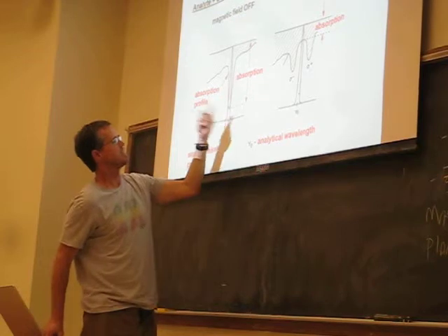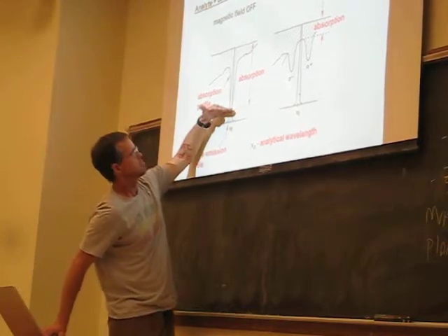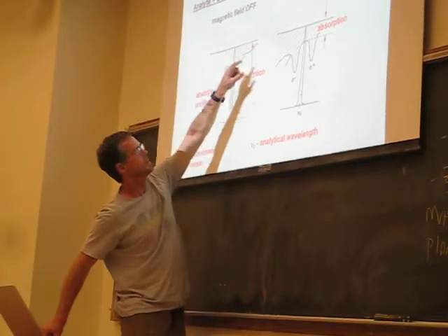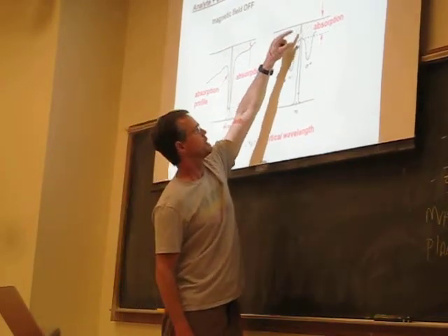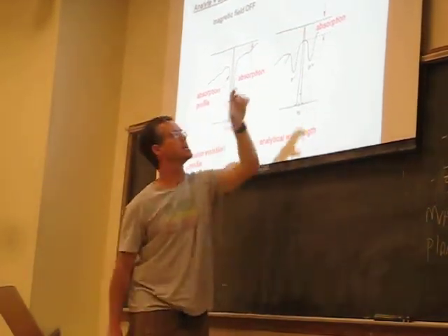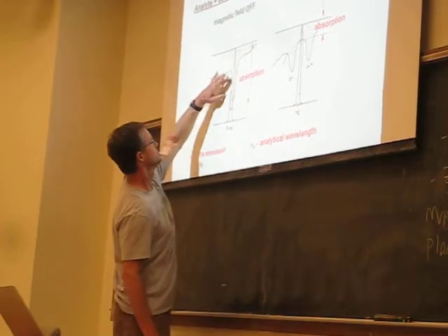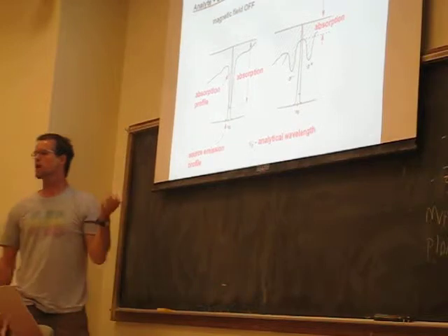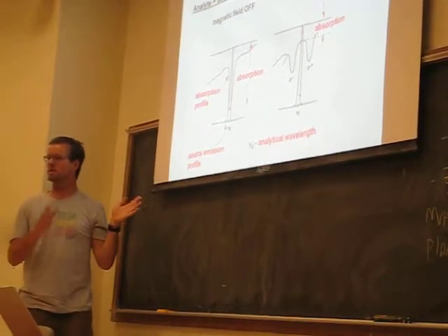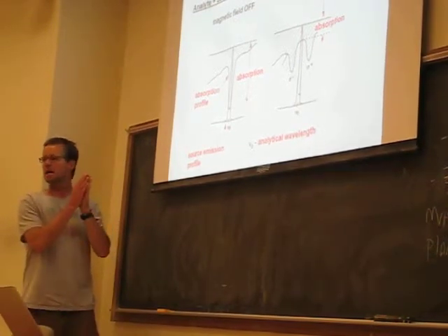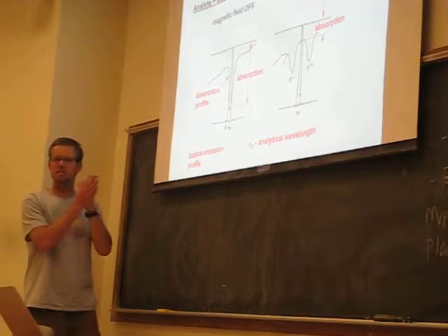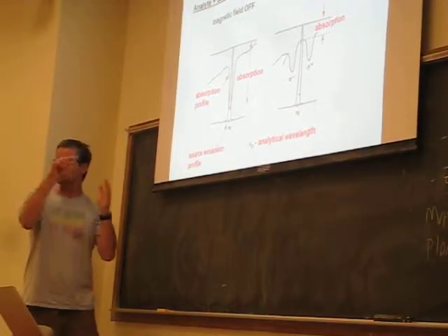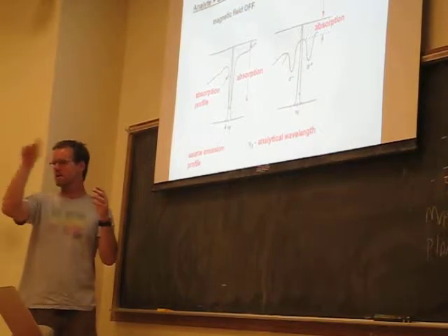And so by cycling on and off, we measure atomic plus non-atomic absorption when the magnet's off, and when the magnet's on, we're measuring only non-atomic absorption, and we calculate the atomic absorption by difference. And it does a much better job than a deuterium arc lamp, because here we're doing correction based specifically on the atomic line splitting, as opposed to using broadband emission to generate that background signal.